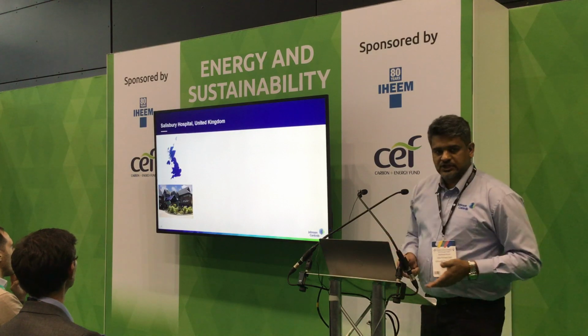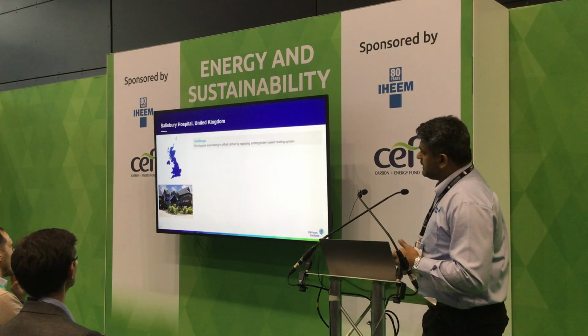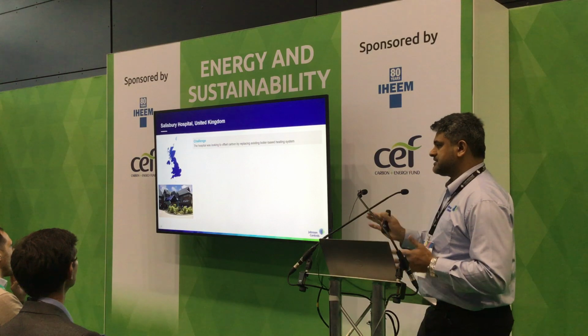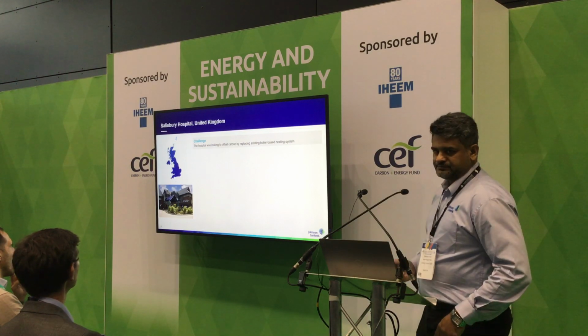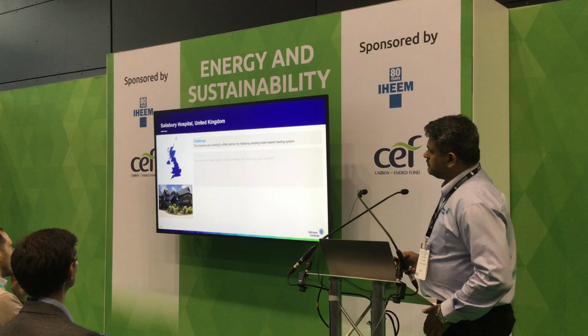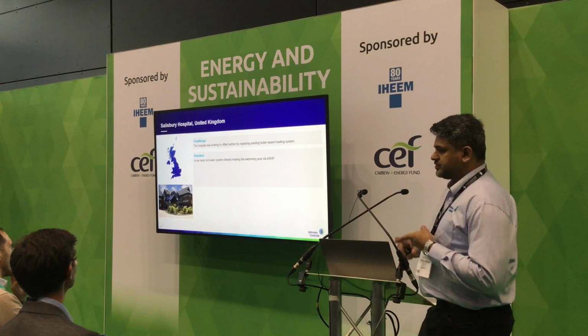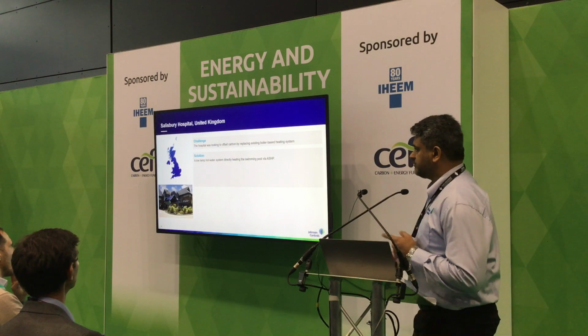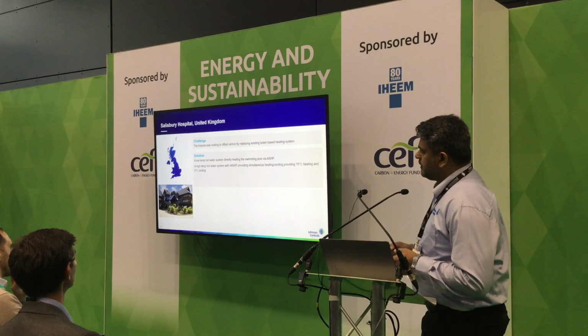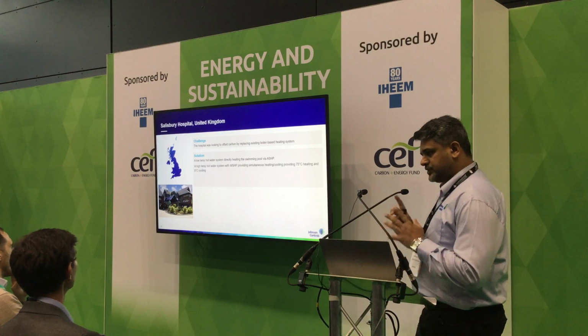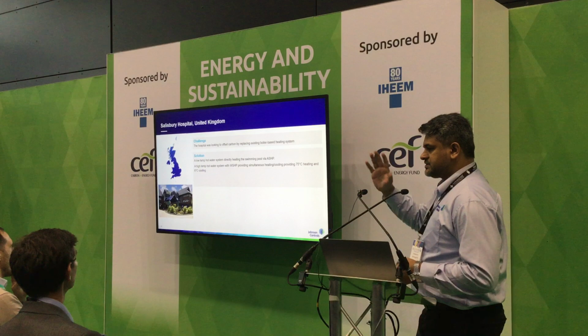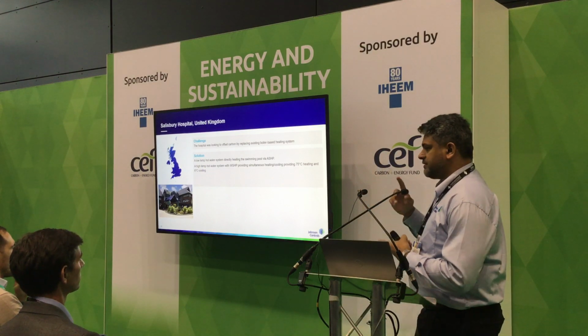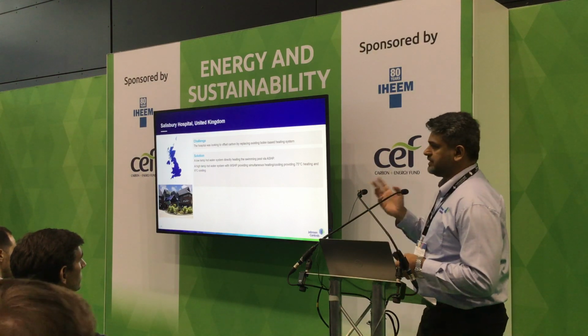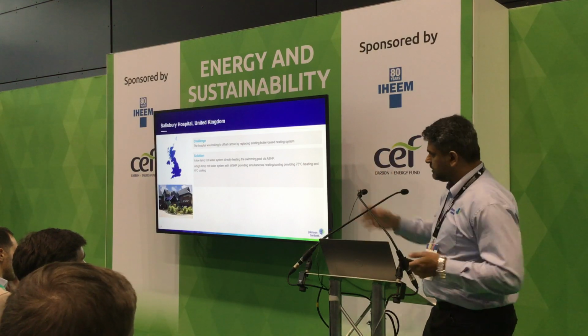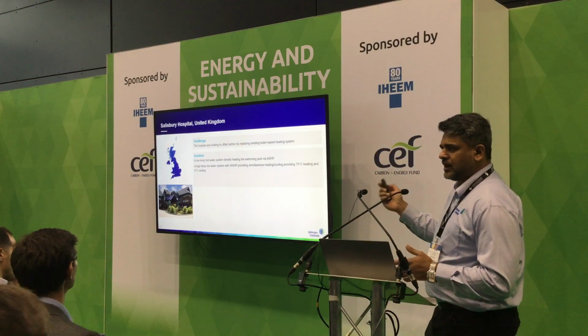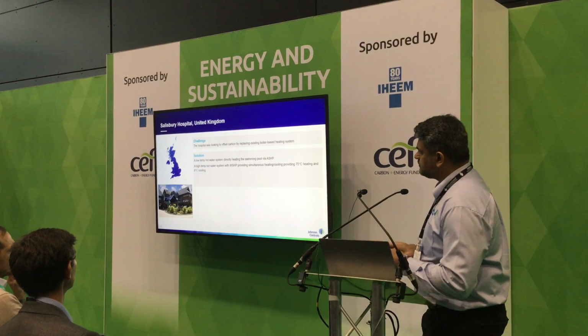Something closer to home, Salisbury Hospital. That hospital is looking to offset carbon by replacing their existing boiler-based heating system. So we implemented an air source heat pump directly to heat the swimming pools. There was a high temp water system with a water source heat pump, which was simultaneous heating and cooling. So you would get 75 degrees of hot water and 6 degrees of chilled water from the same equipment. And this is about a megawatt of capacity.